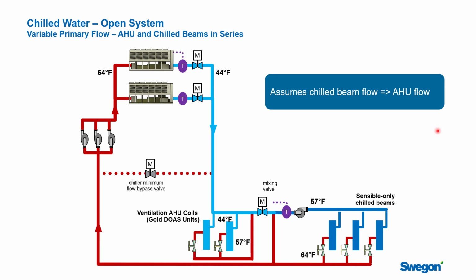And so there's a couple of things we want to talk about with loads. The first one is, I want to remind you that this load is going to behave very specifically. This is dehumidifying and cooling outside air. And so the load on this system, this loop that serves the air handling units, is really proportional to your outside air conditions, particularly your enthalpy. And so as it cools off in the fall and into winter, this load will linearly follow that load outside. This load is about internal heat gains.